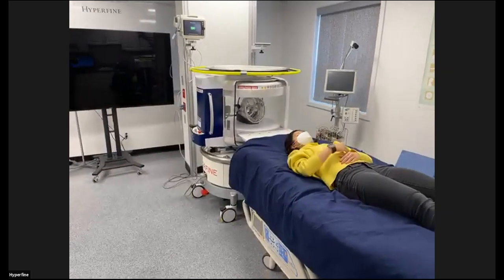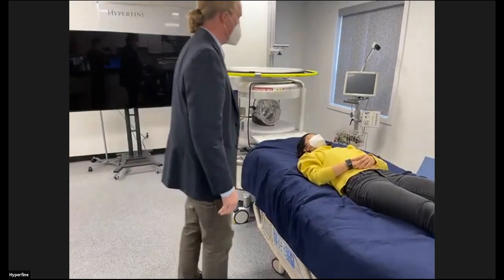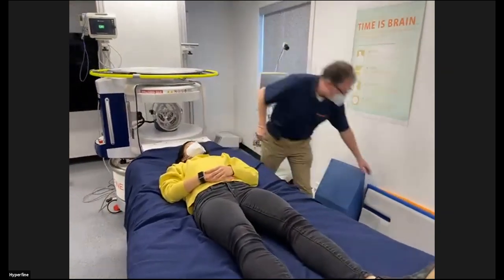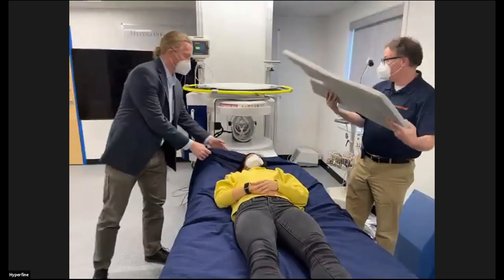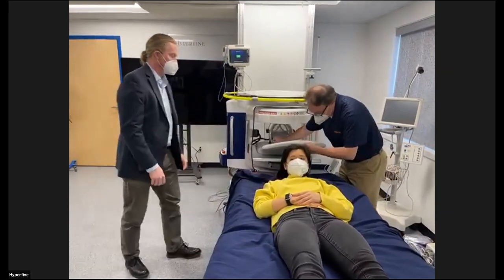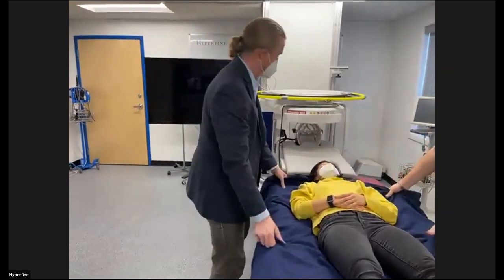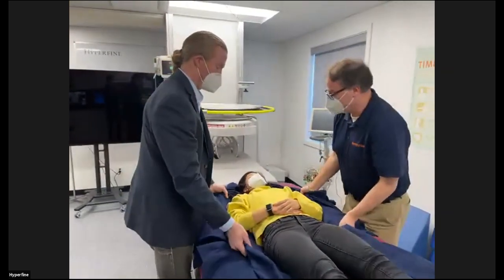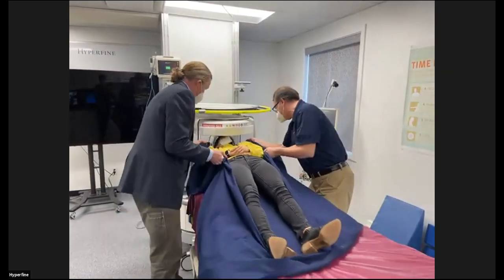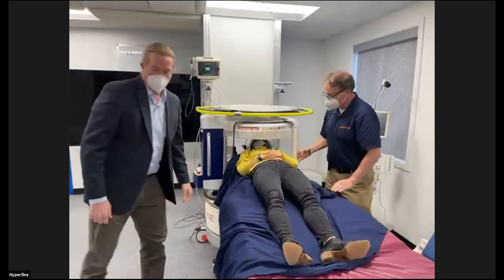We have our patient volunteer waiting for her scan. Chris is parking slowly and pulling the bridge down to cover the gap. He's grabbing the power cord — a standard hospital-grade cord with a three-prong outlet, 110-volt, 15 amps or less — and plugging it in. Today we're using an ethernet connection for convenience, but we can also connect via Wi-Fi at 2.4 GHz. The scanner is powered on. We can open the RF screen on one side to easily access the head coil.